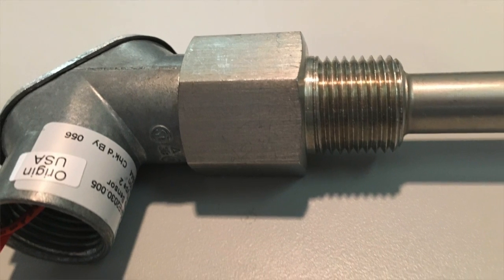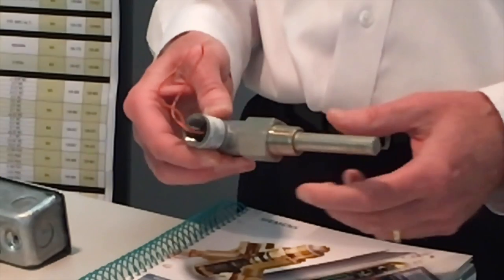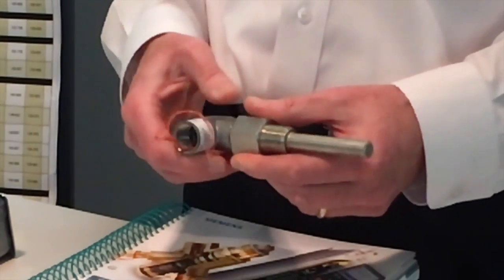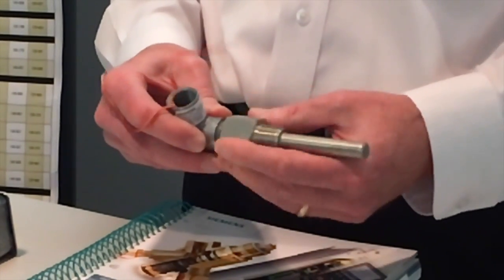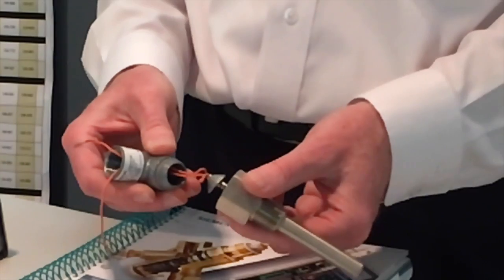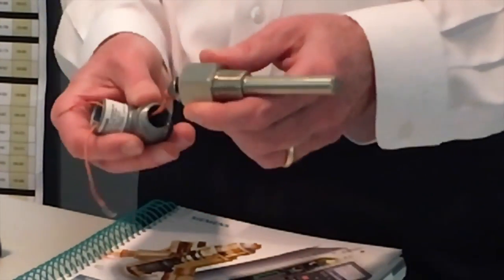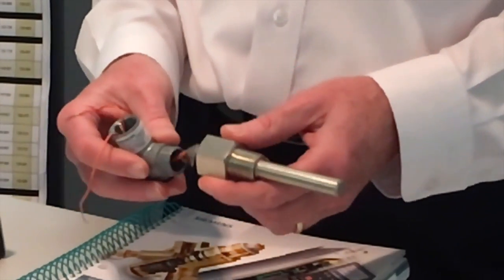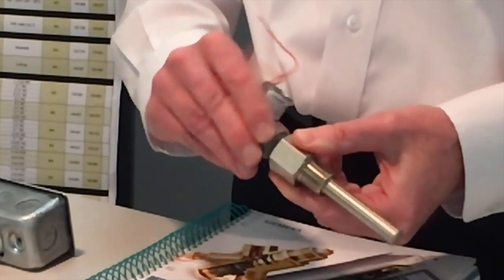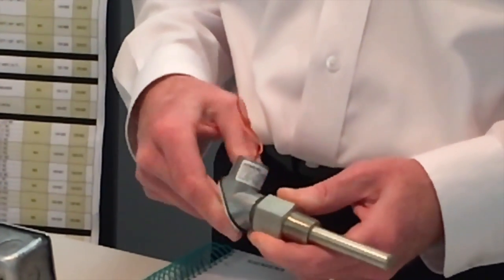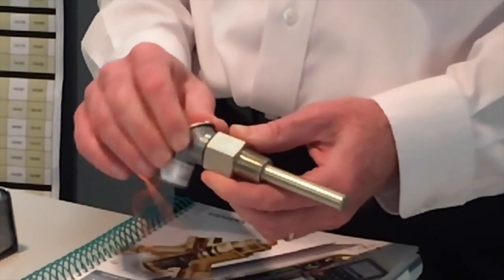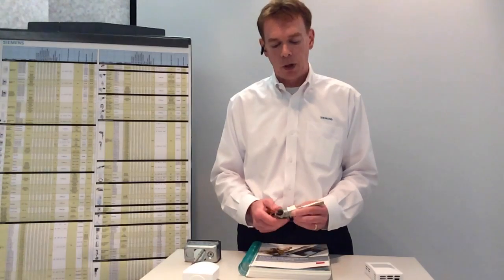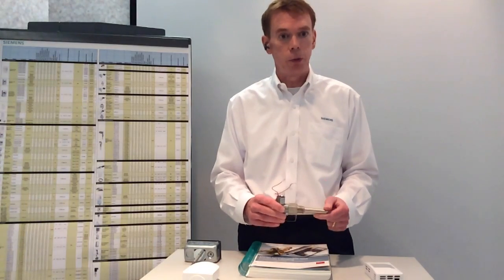What's somewhat unique about the Siemens immersion temperature sensors is one part number includes both the sensing device, which is here in the thermal well, and the thermal well itself. With some of our competitors, you have to order the sensing element separate from the thermal well, and they arrive in 2 separate pieces. Ours arrives in a single piece, ready to install.